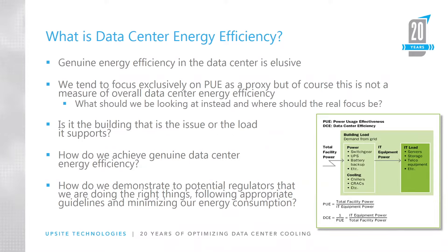Where should the focus be? What is energy efficiency in the data center? Is it all about the building — is the data center the building, or is it more than that? Surely data centers are about the service being hosted within the building. If you've got no IT load in the building, the building doesn't consume any energy. The building puts a slight overhead on the energy consumed by the IT load, and that is effectively PUE.